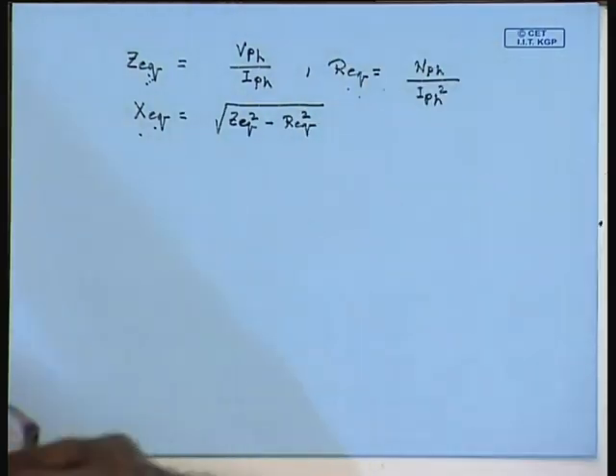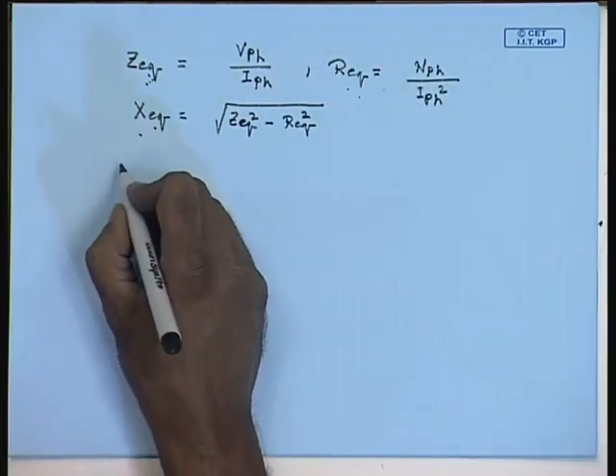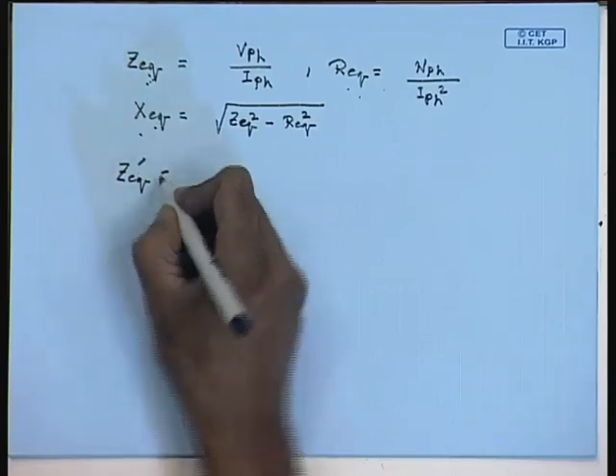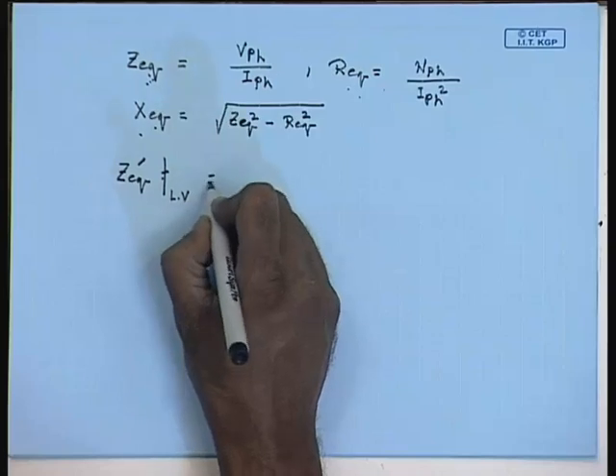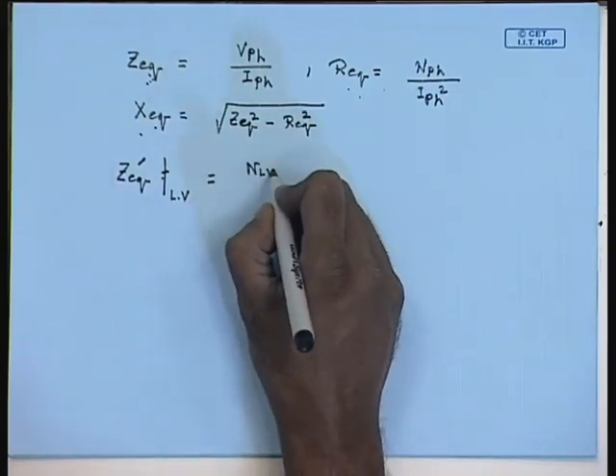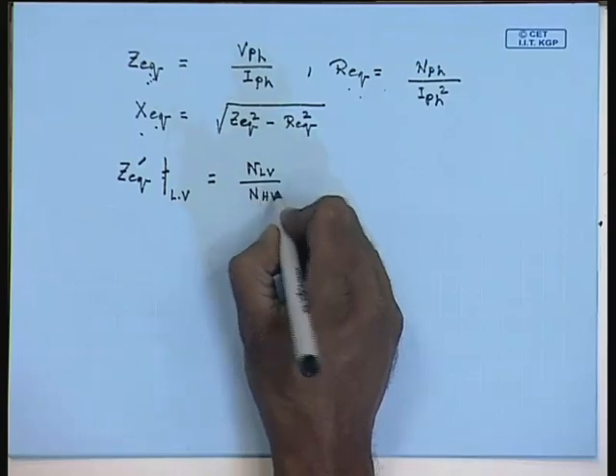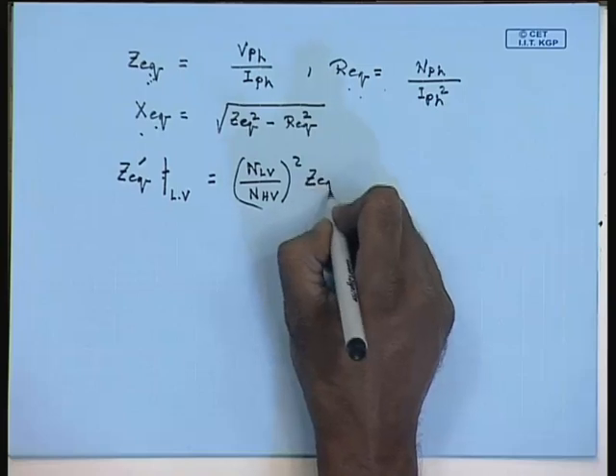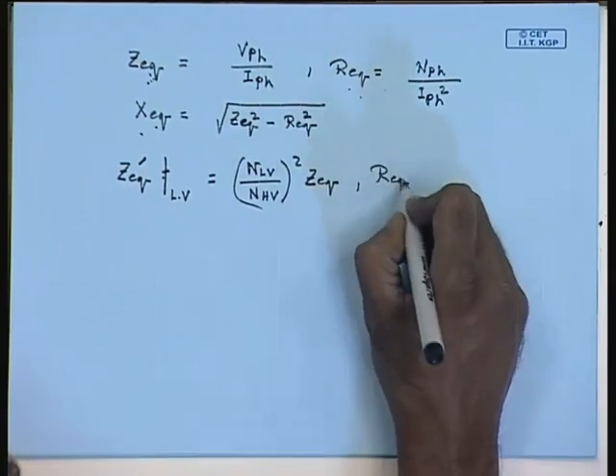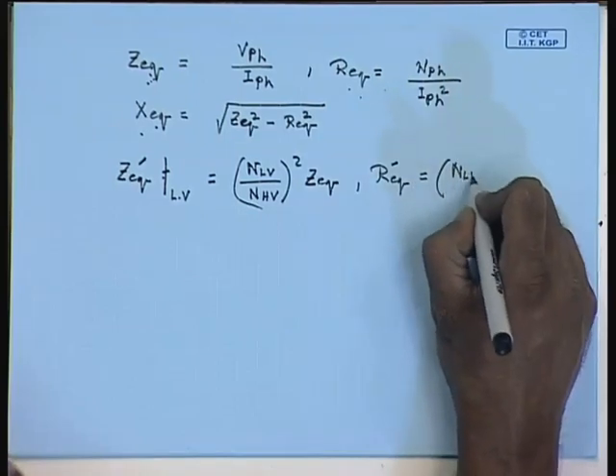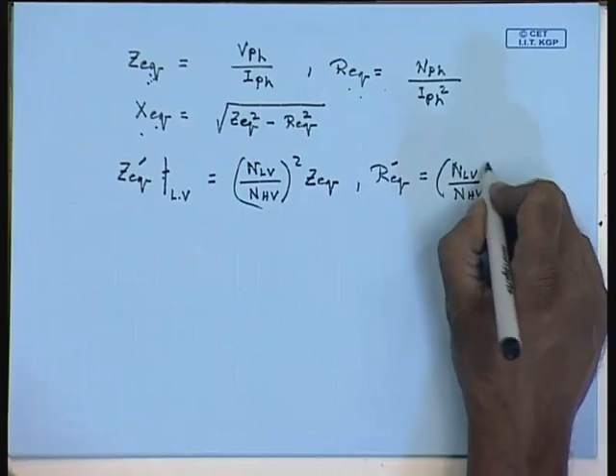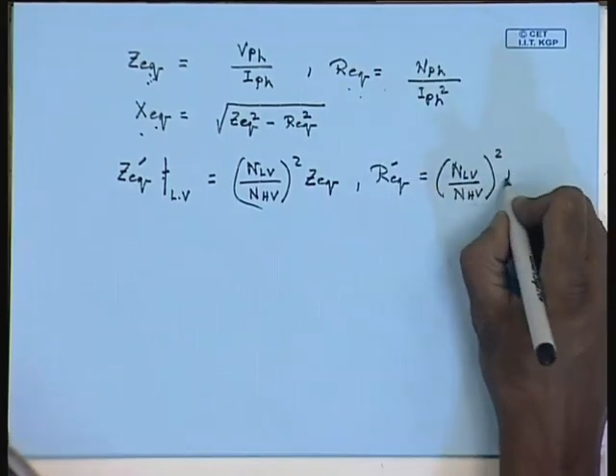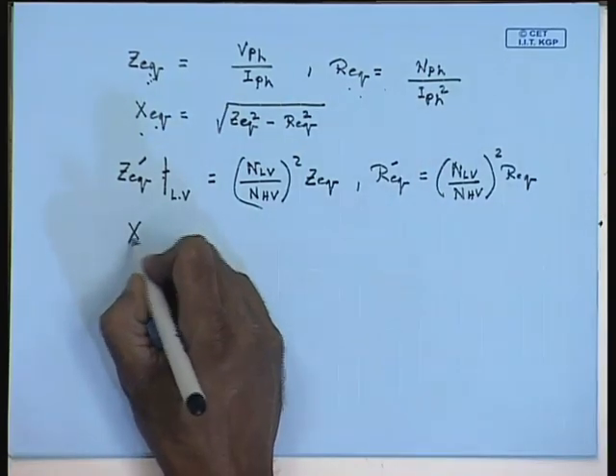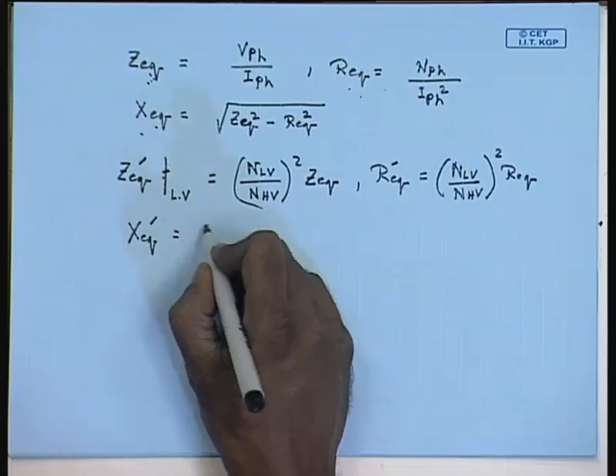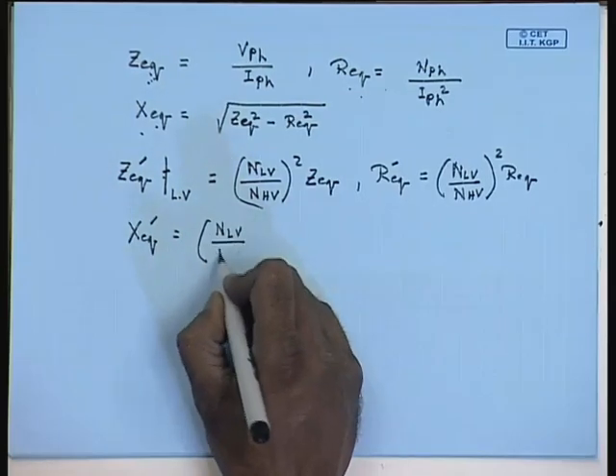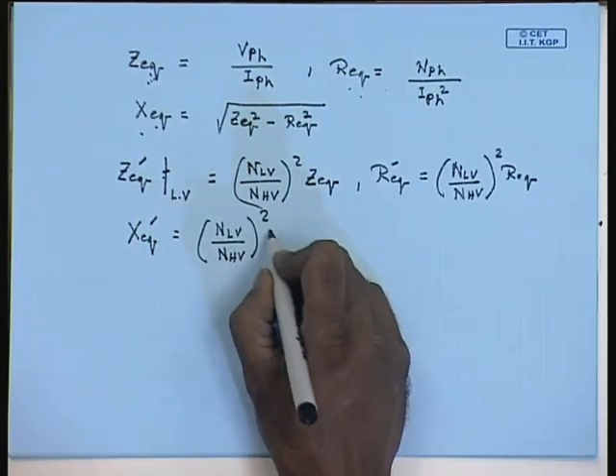For example, the series branch parameter can be converted to the low voltage side by the following relationship, that is ZEQ dash referred to the LV side will be equal to N LV by N HV square into ZEQ. REQ dash will be equal to N LV by N HV square into REQ. XEQ dash will be equal to N LV by N HV square into XEQ.